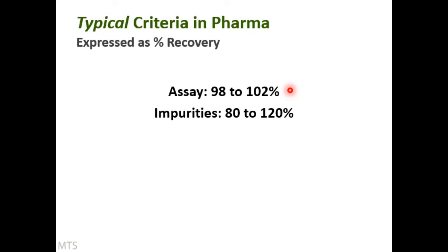So even if you have a systematic error in the method, you'll still get a good result in terms of whether it's passed or failed. Your risk is that when it's close to the specification limits, it's OOT, then it might actually register as an OOS result if it's on that basis. So if you have a negative bias at this end or a positive at this end.